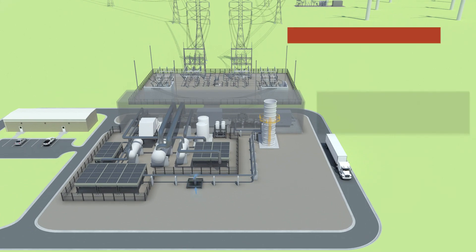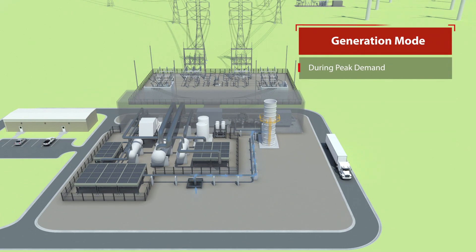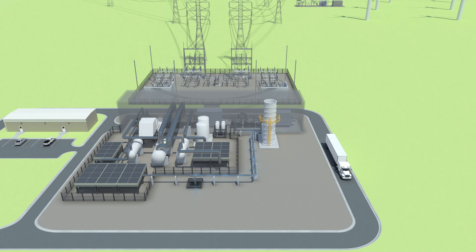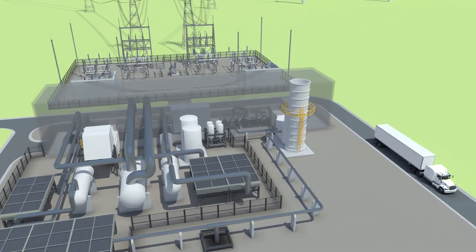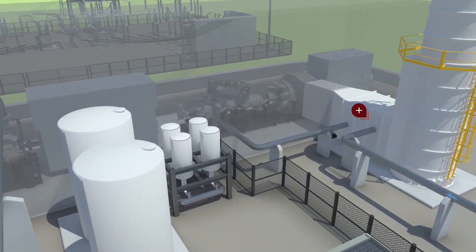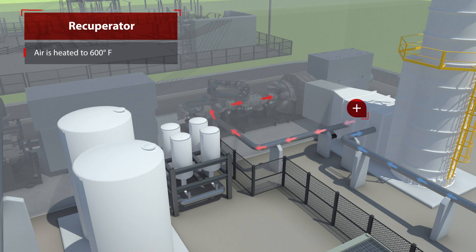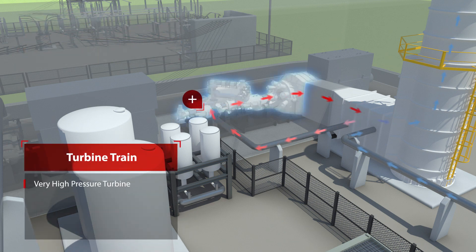When consumer demand is high, the plant then goes into generation mode. The compressed air is released from the cavern into a heat exchanger called a recuperator, where it's heated to 600 degrees Fahrenheit. Next, the hot air is expanded in a high-pressure turbine, where natural gas-fired combustors heat the air to approximately 1,000 degrees Fahrenheit.